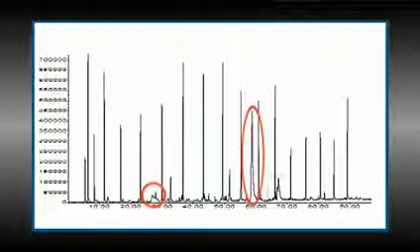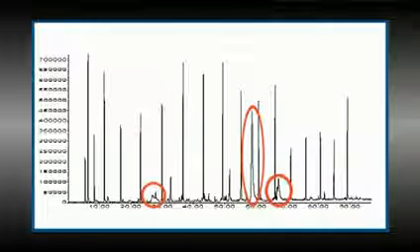Have we gotten all our ghost peak problems? Not yet. Another thing we should consider is whether you might be getting carryover from previous injections or semi-volatile contamination. If the ghost peak widths tend to be broader than the normal sample peaks right around them in the same part of the chromatogram, this is usually sample carryover. You'll see two examples on the screen of what carryover looks like. This carryover indicates that not everything is eluting from the column before it cools down for the next analysis.